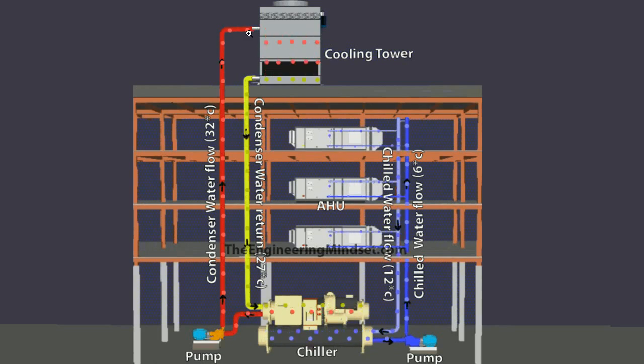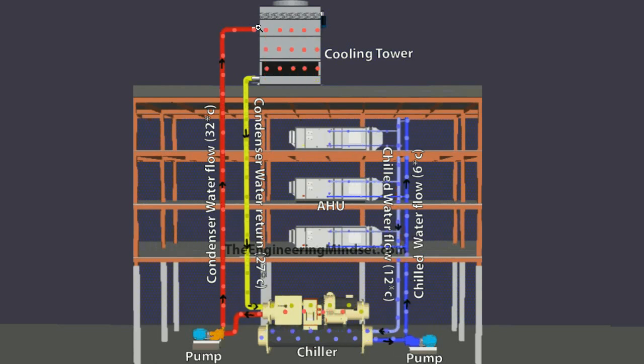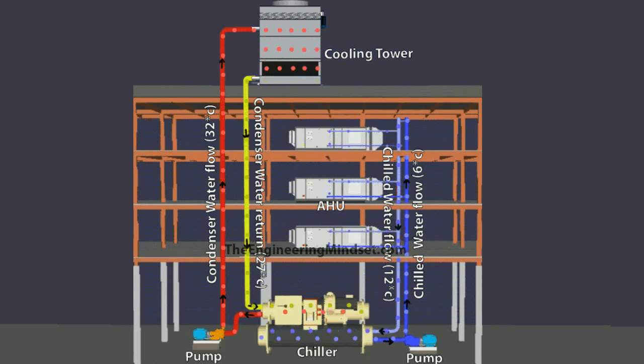With this type of cooling tower where condenser water is sprayed through the cooling tower to reject and dissipate heat into the atmosphere, this is an open system. Whereas the chiller refrigerant loop is a closed system, the cooling tower loop is open, so water is sprayed and air and dirt can get into this system. What comes into this system gets sent down into the condenser, and this presents a problem because you get an effect known as fouling occurring on the inside of the condenser.